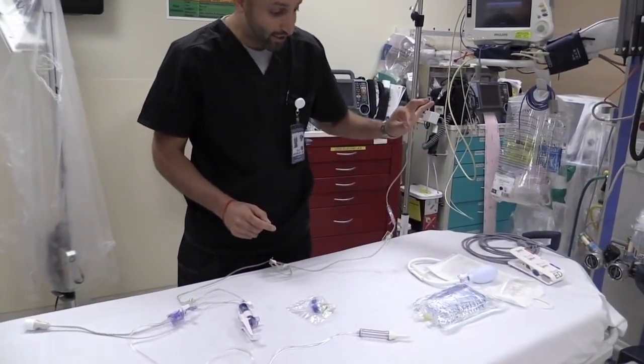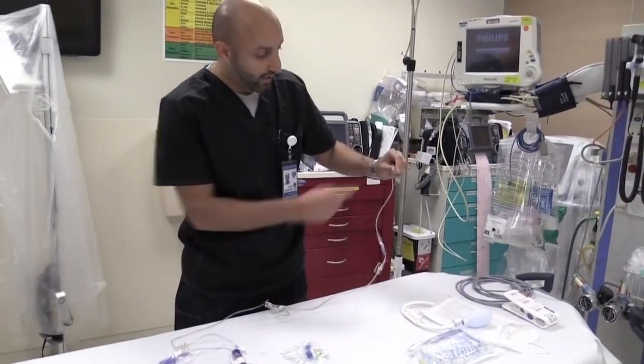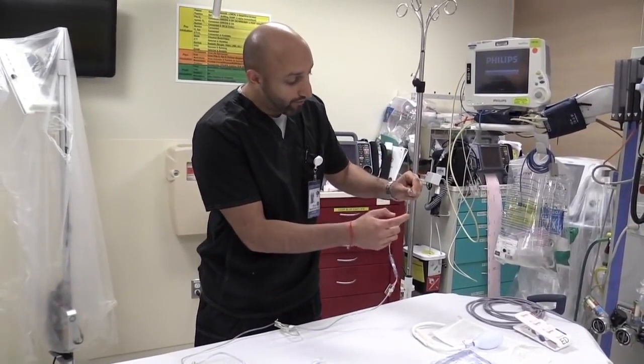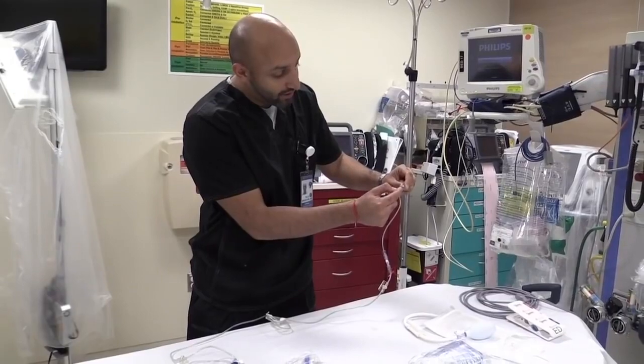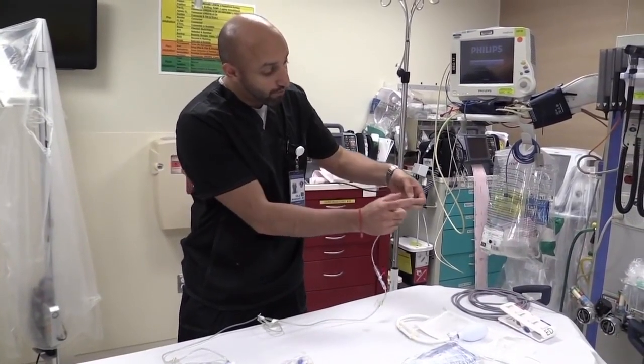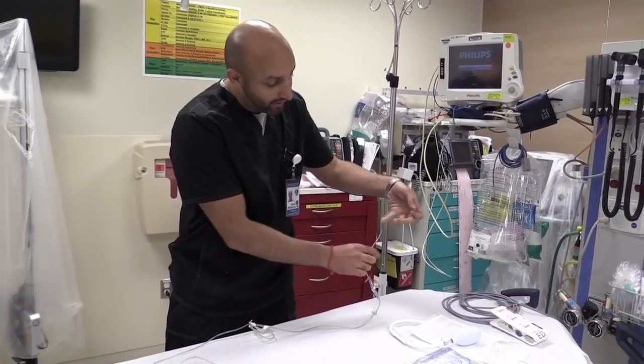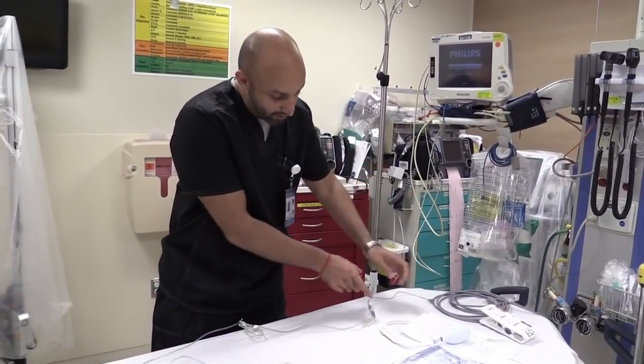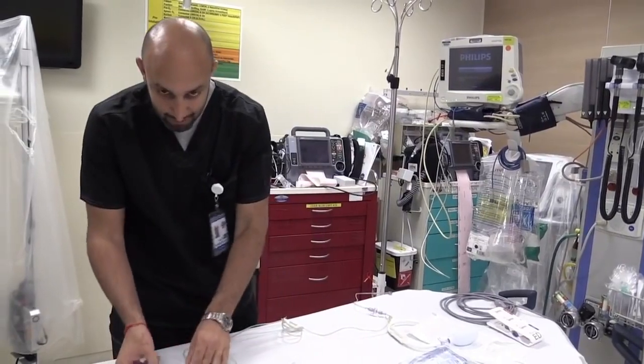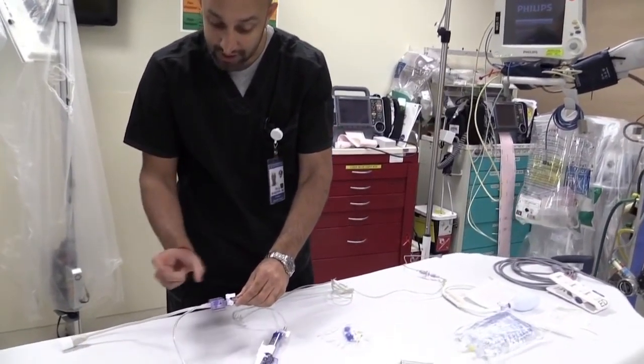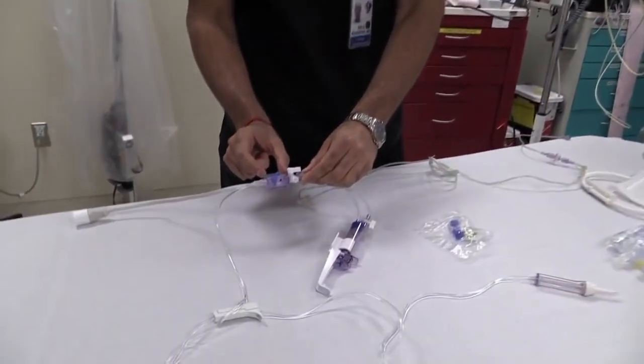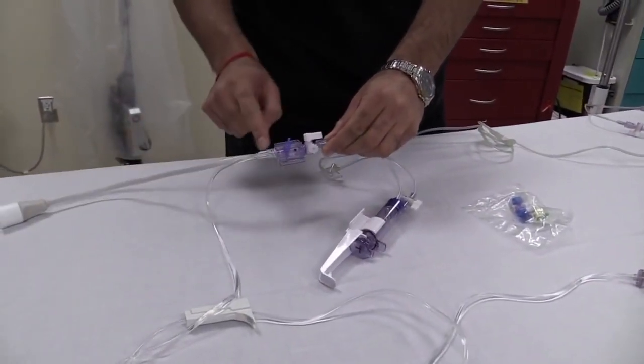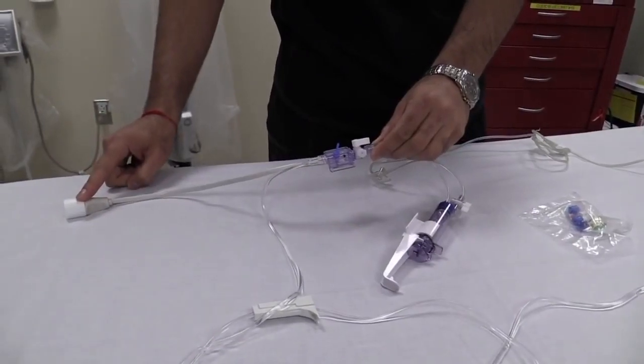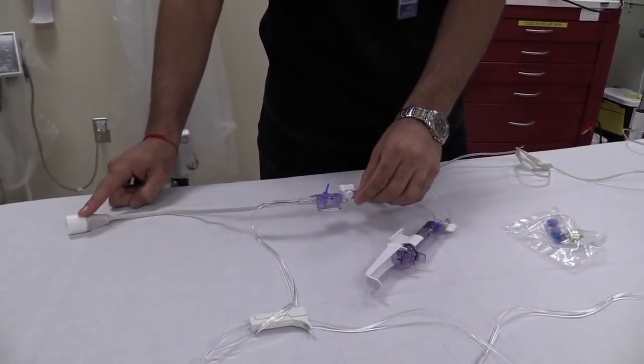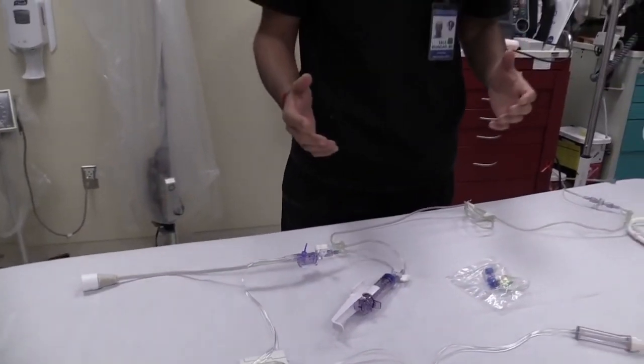So what happens is this end is going to be connected into the patient, into the arterial line. As soon as that pressure wave from the patient's artery goes into this port over here, it's going to move this column of fluid that's in here a certain amount in certain pulsations. That's going to essentially get detected by this transducer right here. And as soon as it detects that amount of movement, it's going to convert that into an electrical signal, which will be outputted here and onto the monitor, and that's what you're going to see as your arterial blood pressure. So that's the overview, that's the big picture. Now let's break it down into each of the individual steps of what you're going to do.